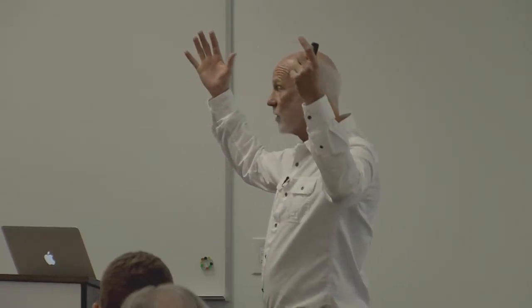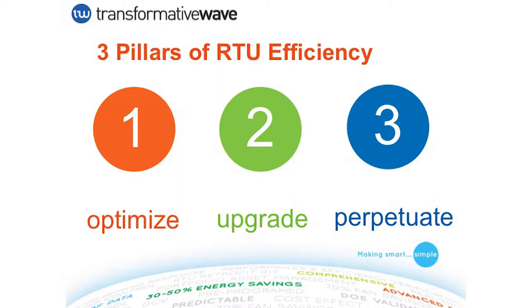Many of you in facilities using pumps or fan systems have probably applied VFDs and seen energy savings as a result—it wasn't the original configuration, just part of an upgrade. Big VAV systems that used inlet vane dampers get retrofitted with a drive—same concept. It's an actual hardware upgrade that gets you to a different level of efficiency.